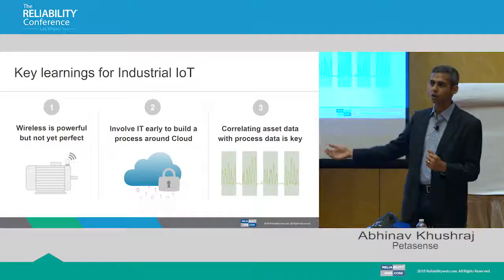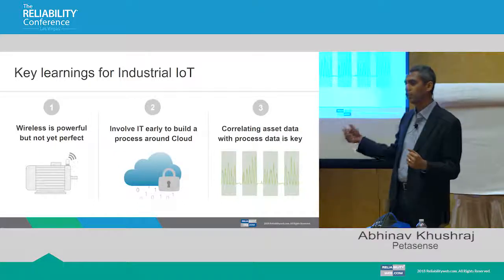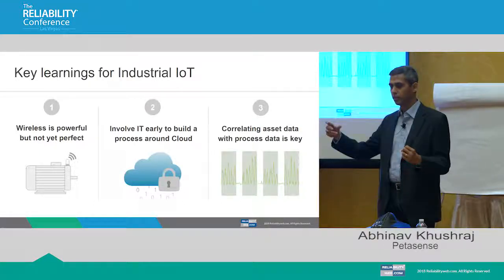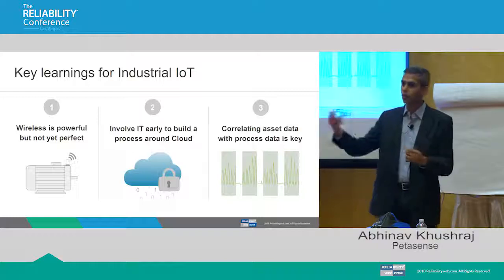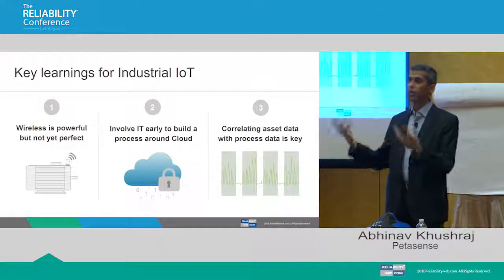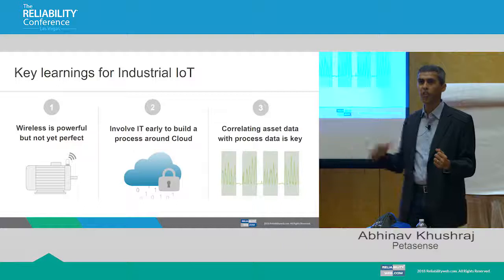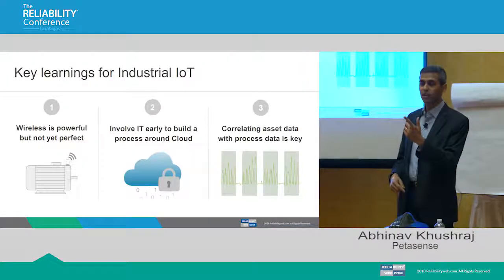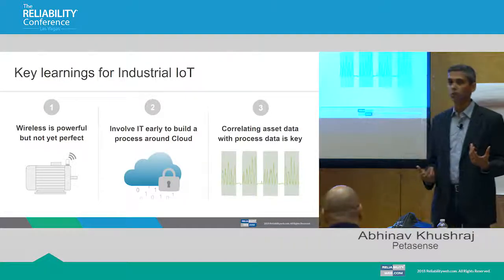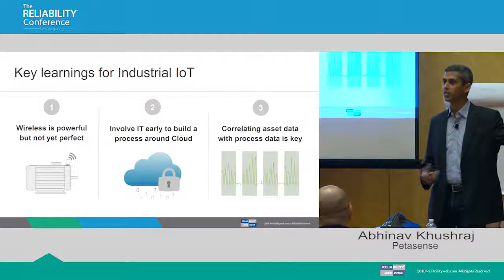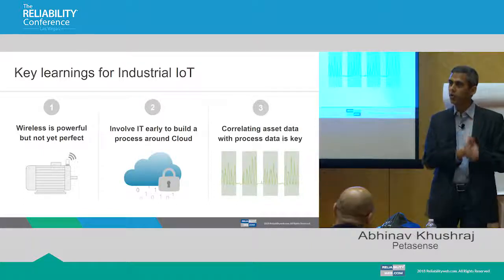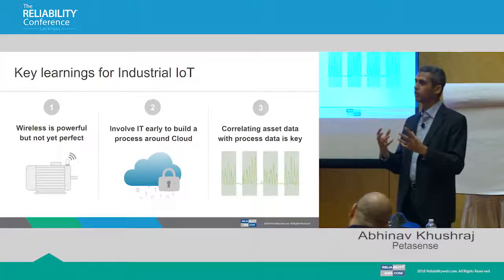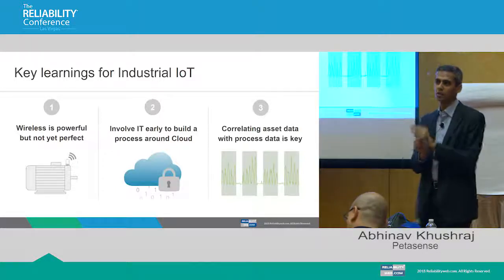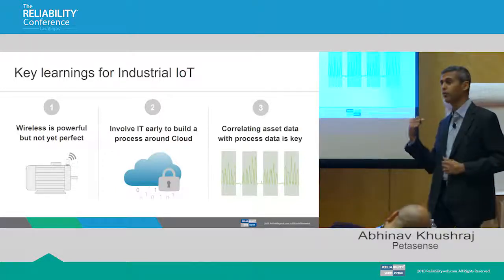So how do you measure load? In the case of an air handler, there are some pressure sensors you could use to get the pressure, or if you have a pump, you could put a pressure sensor and look at the load along with that. If you want speed, monitor the running speed. How do you get the running speed? You can use your current sensor, since the motor running gives you the running speed from that. So the multi-parametric view of a machine is extremely important, and that's how we would model the data science going forward.